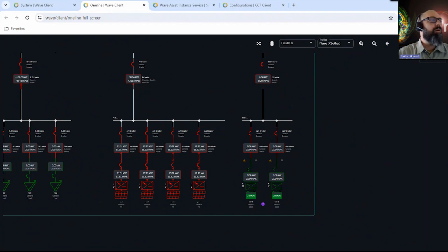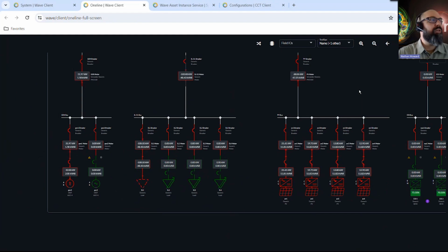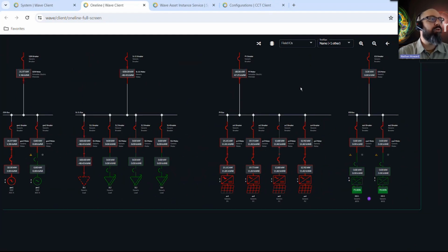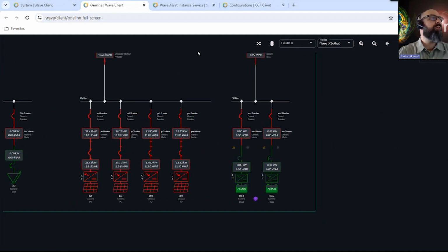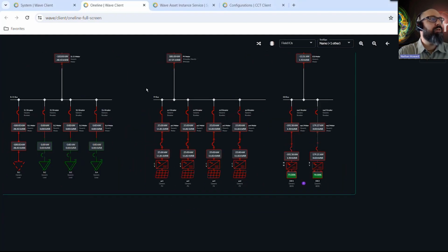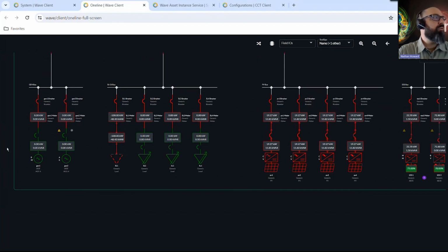So kind of back where we were, we've got one generator online providing that frequency and voltage master service. We have our PV online. We're using as much as we can. So now we'll go ahead and switch the battery over to be remotely controllable and available to the Wave microgrid controller. And as we see those become available, we'll see Wave brings them online, closes the breaker, and starts pulling power from them to meet the needs of the system. And when those now are available, we see that it's backed off the conventional generation, shut that down. So now we're operating in a purely battery and renewable operation to meet our loads.